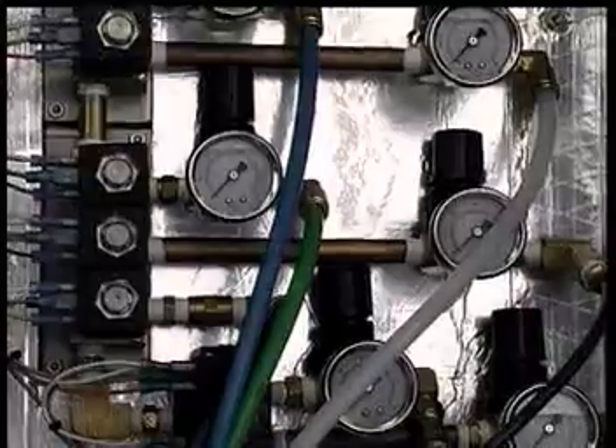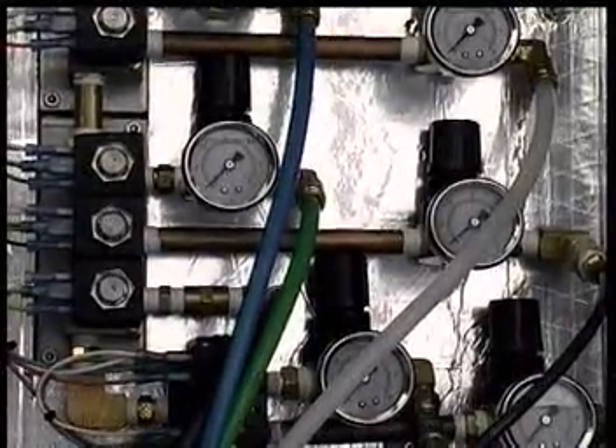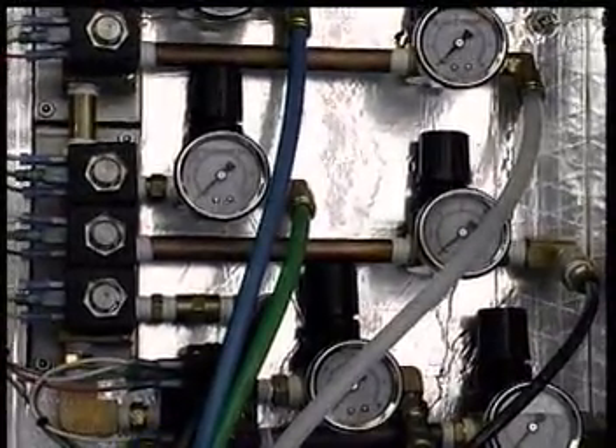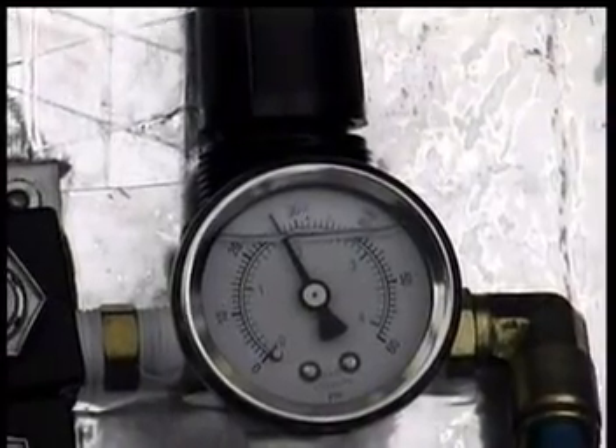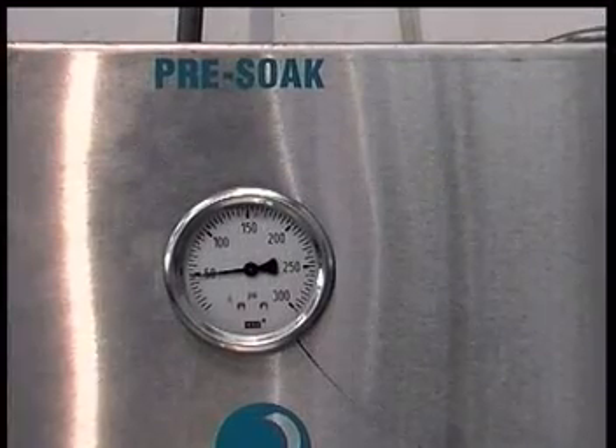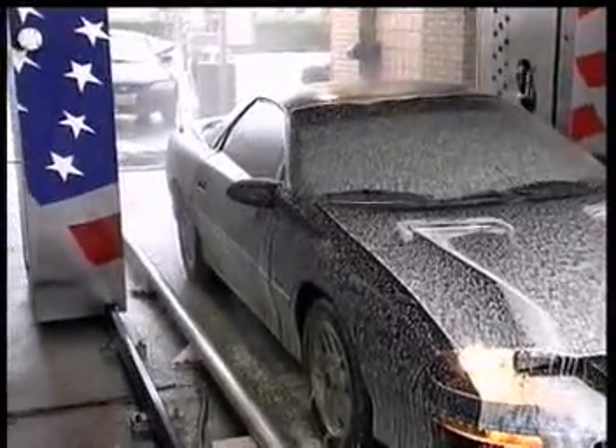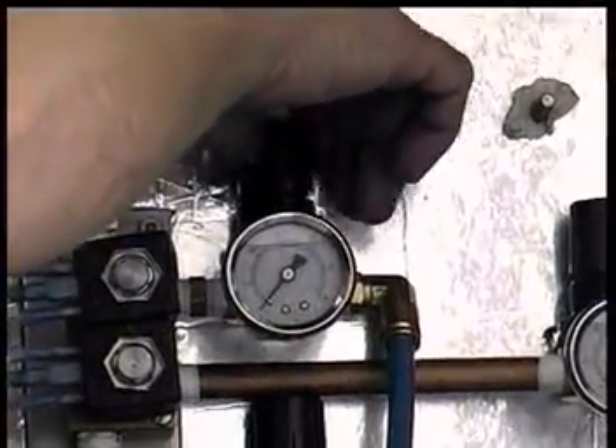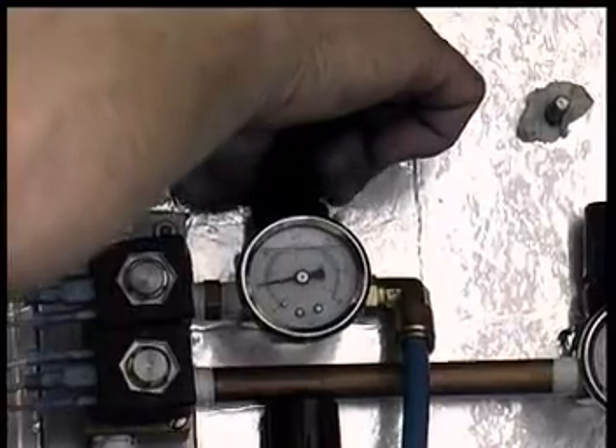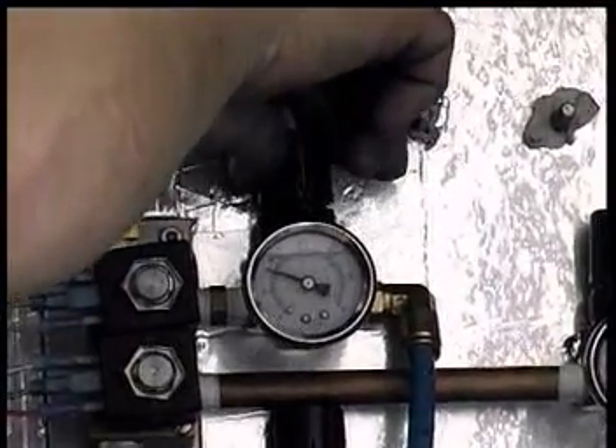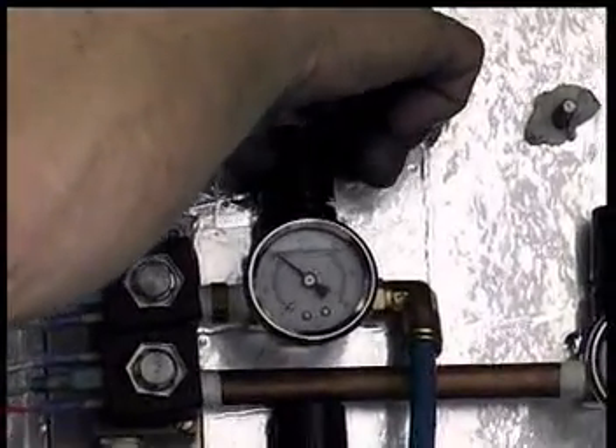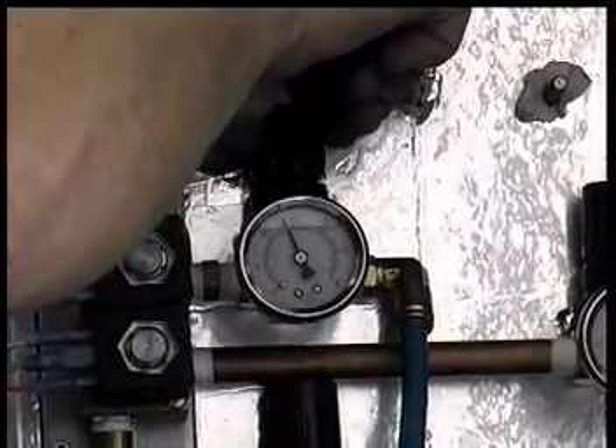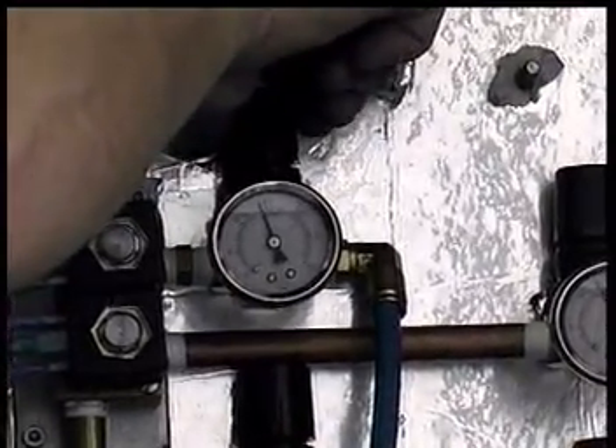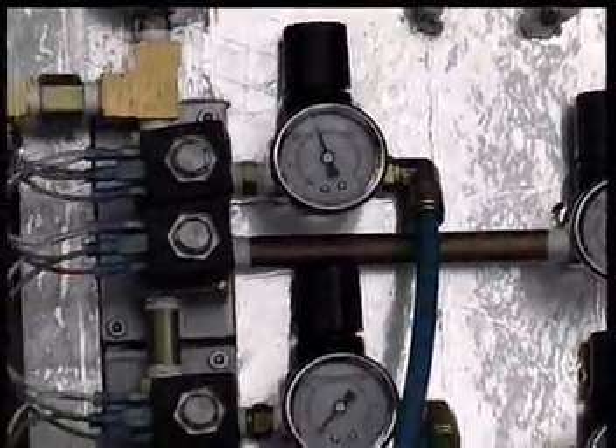The low-pressure regulators are located in the low-pressure manifold box on the driver's side of the gantry. These regulate the air pressure to product ratio. Adjusting the air pressure will produce a more or less foamy consistency in product application. To adjust pressure, lift the adjustment knob and turn it to the right for increased pressure and to the left to decrease it. Remember, the air pressure should always be less than the product flow pressure. Usually there is a 10 to 15 pound difference.